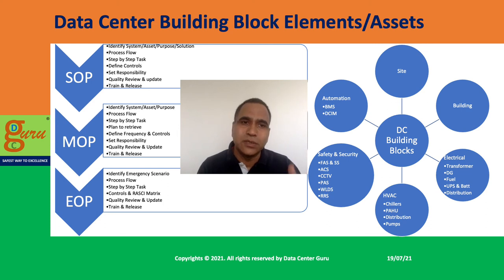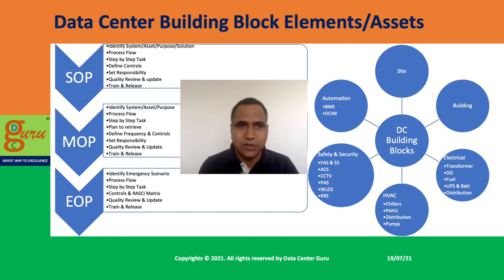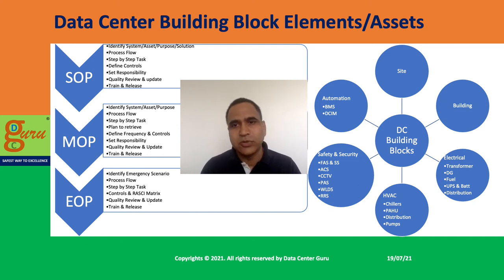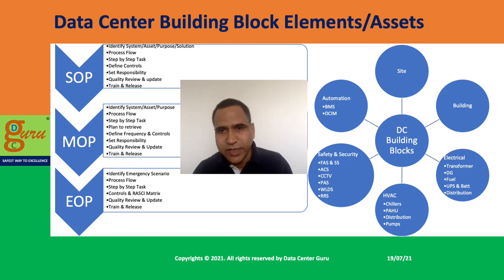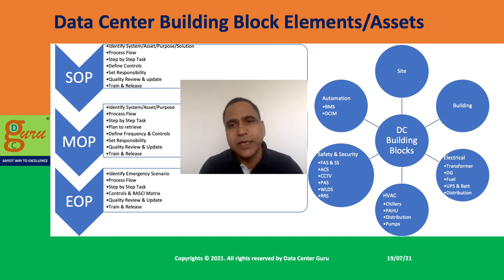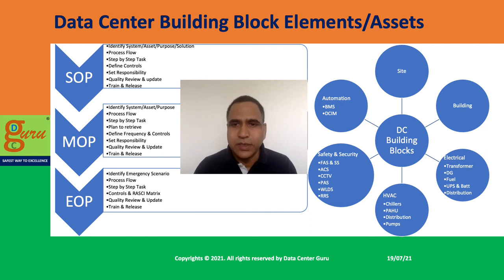Similarly you develop MOPs — find asset, system, purpose, then create the process flow step by step. Here also plan a return path, because whenever you are doing maintenance, each activity has an expected outcome. You check whether you are getting that outcome; if not, follow plan B and retrieve. You need to recheck the system before doing the maintenance again — otherwise you invite the risk of outage in your data center.